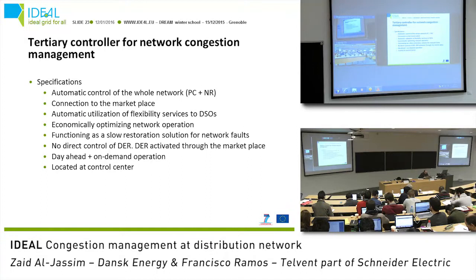Some of the specifications of the tertiary controller, or the network reconfiguration, for network congestion management: it automatically controls the whole network, and it's the only algorithm that has a connection to the marketplace. By operating once a day or on schedule, it economically optimizes the operation of the distribution network and also functions as a slow restoration solution for network faults. It has no direct control of DERs. The DERs are activated through the marketplace, and it's based on day-ahead and on-demand operation. And it's located at the control center level.